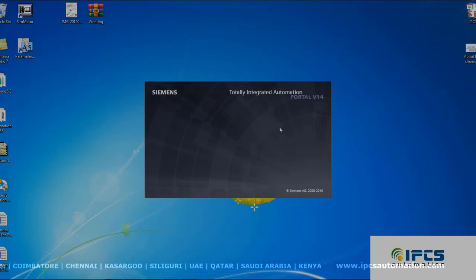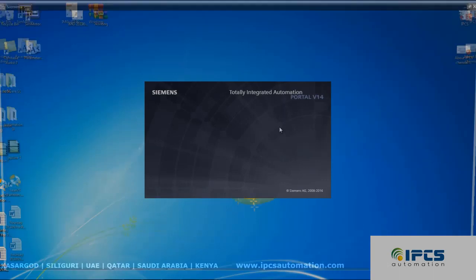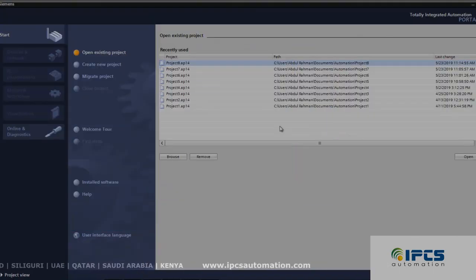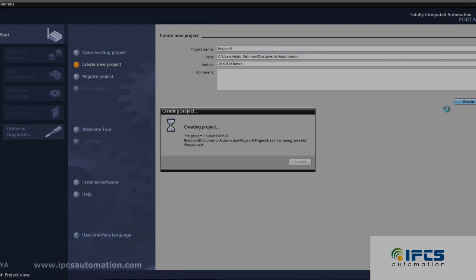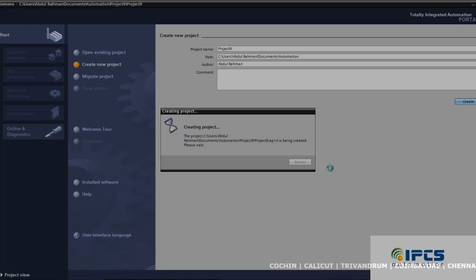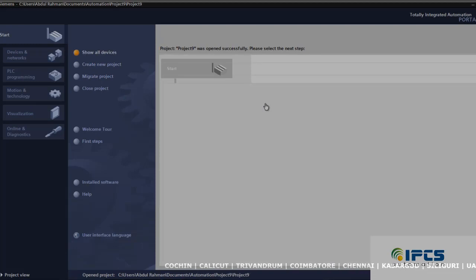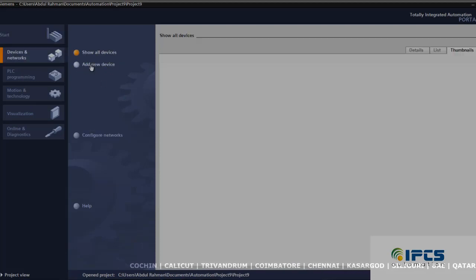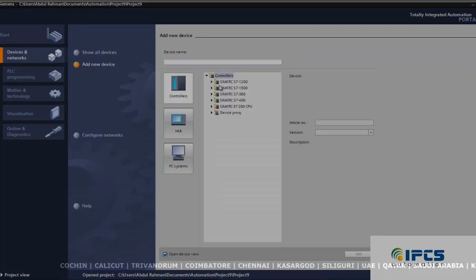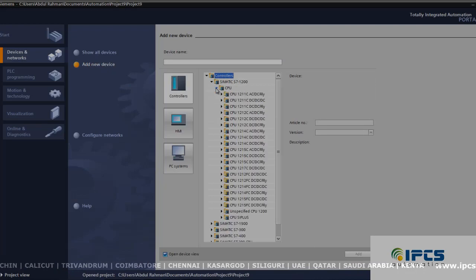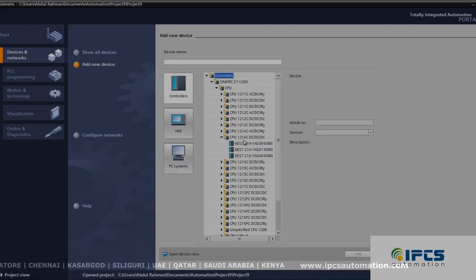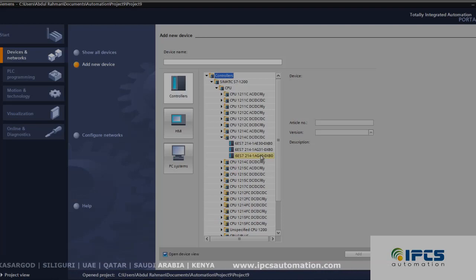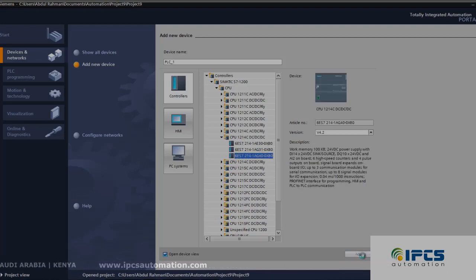We are going to read the real-time clock of S7-1200 Siemens PLC using TIA version 14. First, click create a new project, then create and configure a device. Add a new device and choose your PLC type. The PLC that I am using is CPU 1214C DC/DC/DC with this serial number. Next, click add.